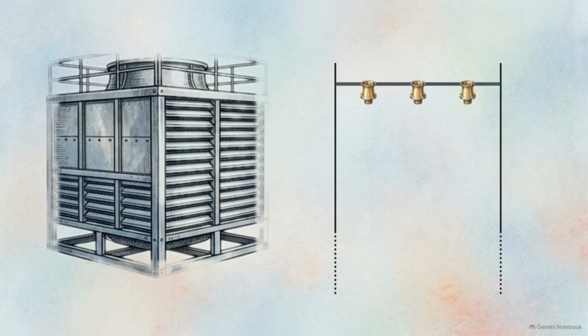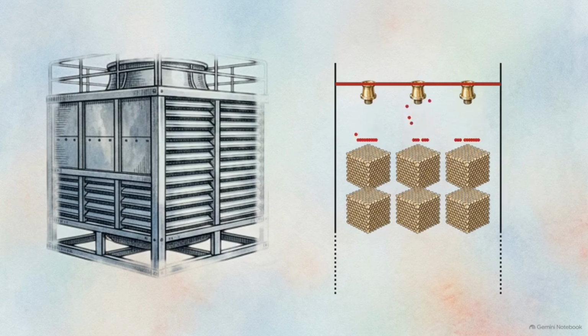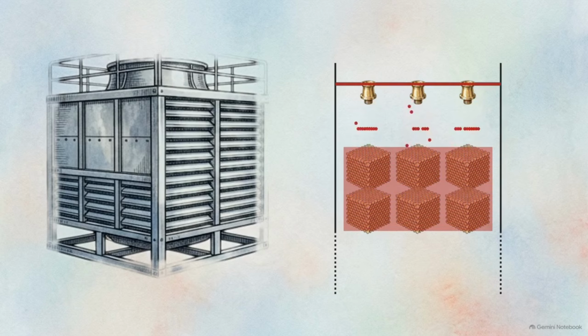To scale this up, hot condenser water is forced through spray nozzles, atomizing the fluid to instantly multiply its surface area. But atomized mist falls too quickly. It needs to pass through a dense honeycomb structure known as the fill. This fill acts as the primary heat and mass transfer engine. It forces falling water to spread into a microscopic, slow-moving film, maximizing surface area and contact time with the air.